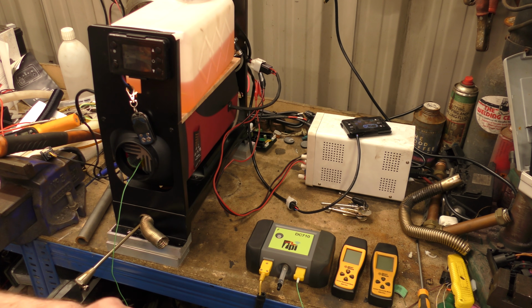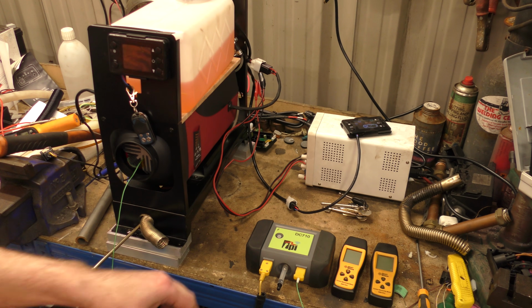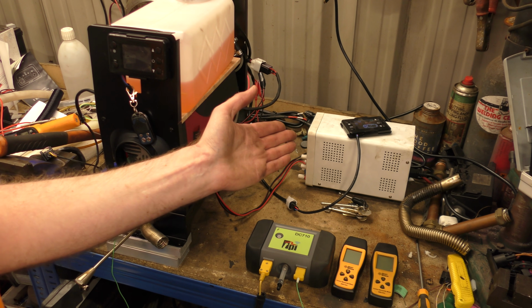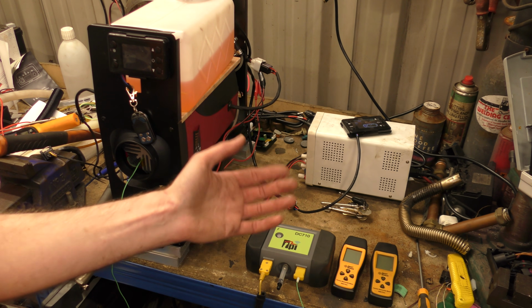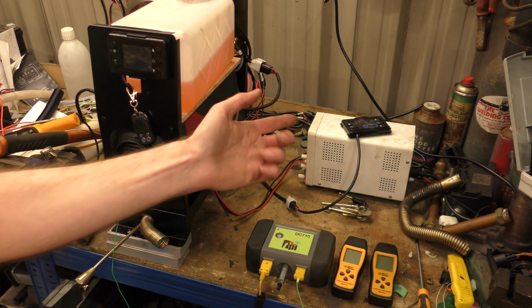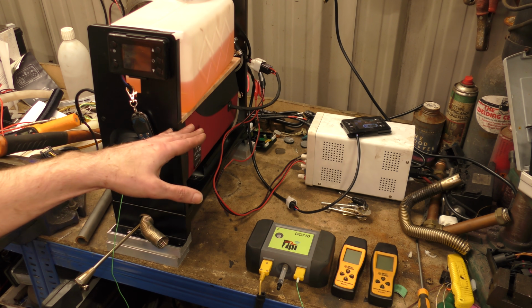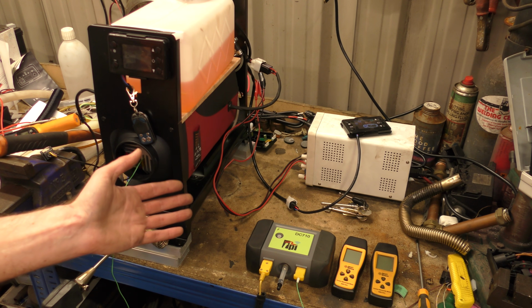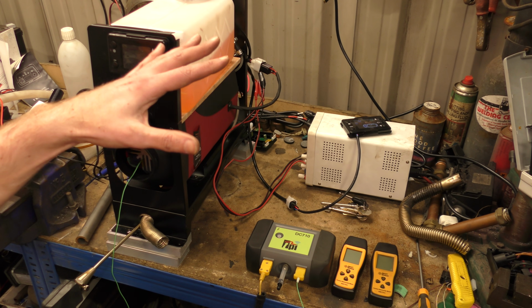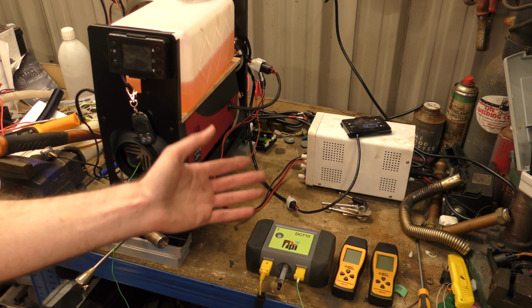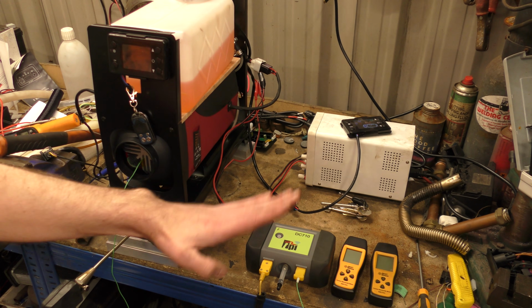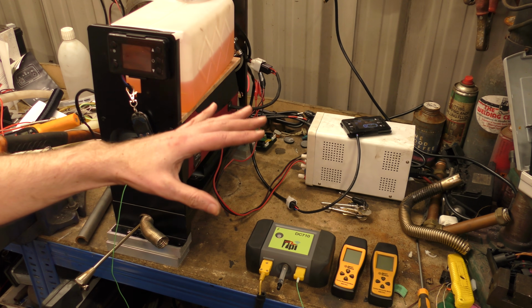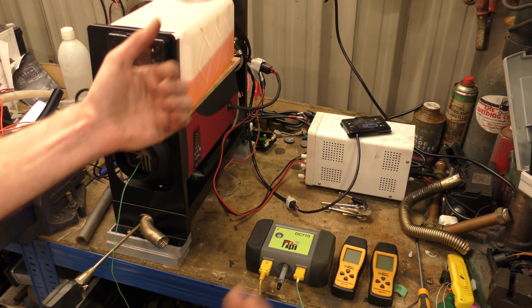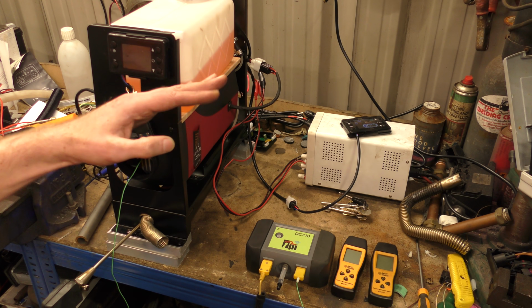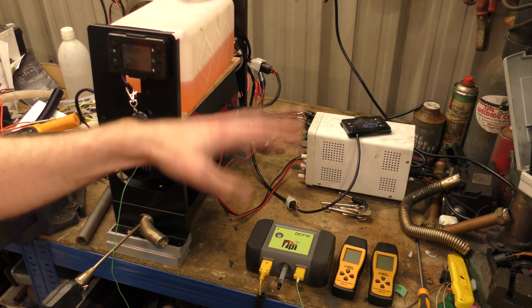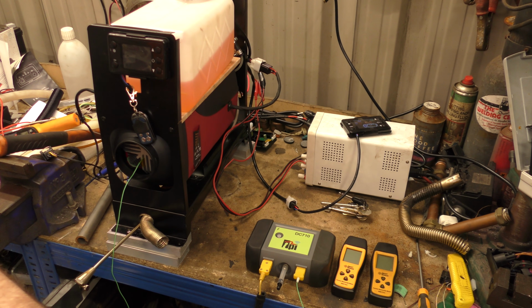I've learned that the fuel and air ratio is more complicated than I gave it credit for. Even though you can set it to 5 Hz and 5,000 RPM, this heater was still pegging the hottest temperature setting and then having to throttle back. As we saw, throttling back makes a lot more carbon monoxide, because it cuts the fuel, the flame dies and drops down, you get a lot of carbon monoxide, then it turns the fuel back up and ramps back up again. We don't want it oscillating between really hot and cold. We need to dial back the fan speed and fuel speed so we can stay hot with minimal carbon monoxide, but also stay under the threshold of the housing getting too hot and throttling back the fueling, because that kills your efficiency and wastes fuel.